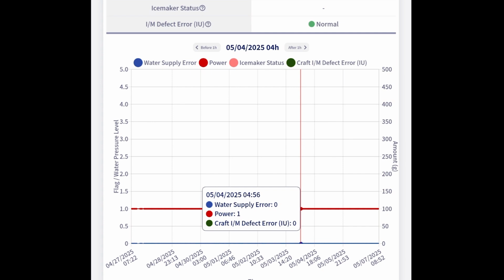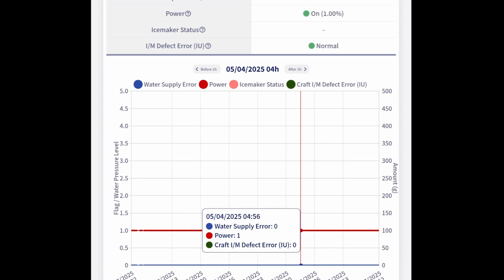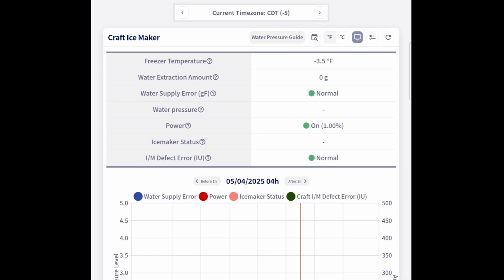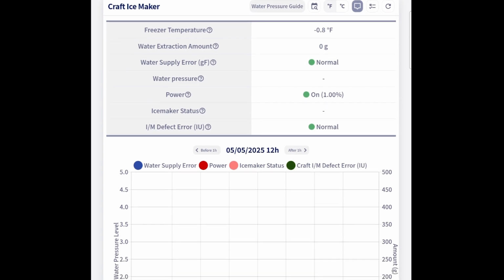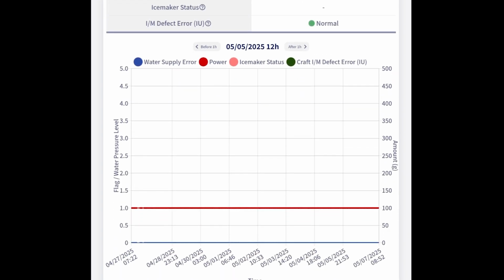If the power was off, there would not be a red bar, and beside power, it would say 0. The table at the top gives you your freezer temperature, and lets you know if the power's on for wherever you've selected on the chart. And if there was an error code, it would show up there also. So not as much information again as the indoor ice maker, but this is an example of a craft ice maker that's working properly because we don't have any other errors on the screen. So next we'll show you some examples of units that do have craft ice maker errors.